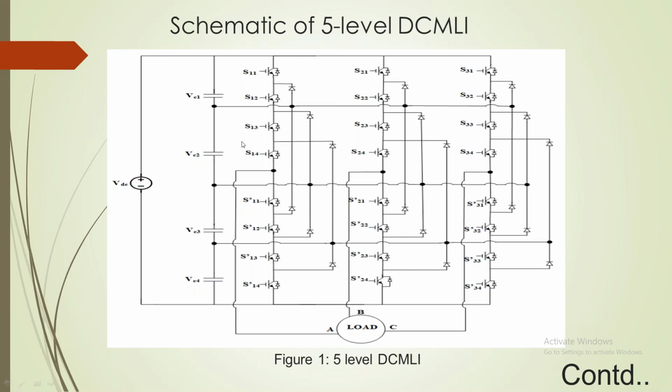So if the capacitor voltages are not uniform, the output levels will not be uniform and the output voltage will be distorted. So we have devised techniques to ensure that the output capacitor, the load, and the supply side capacitor voltages are maintained constant irrespective of the reason by which they are affected. I've already discussed the reasons, right? A few reasons were the tolerance limits of the capacitors, the difference in switching characteristics, and the effect of load, right?